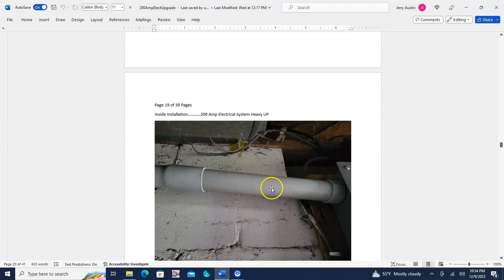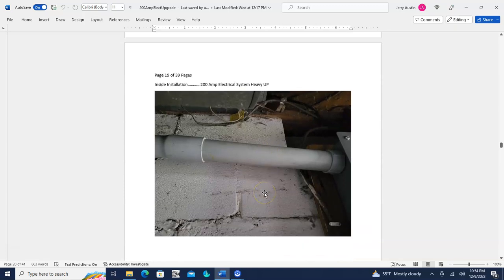Now we're getting into the inside of the house here. And this is not a direct feed through from the meter base into the house. As a matter of fact, the meter base is way over here in this area, and what it hooks into is over here. And this, once again, is a 2-inch PVC pipe. There's a joint there, and this is where it hooks in over here to this box inside the house, the circuit breaker box.